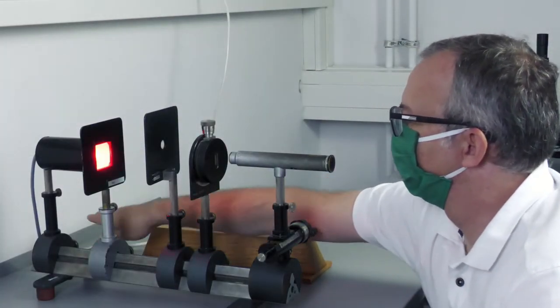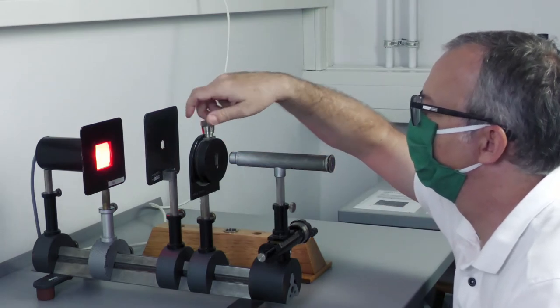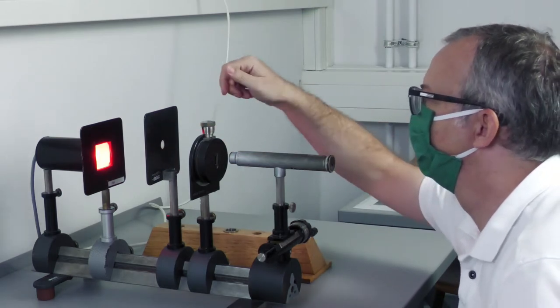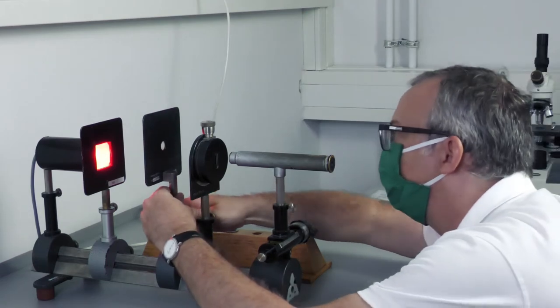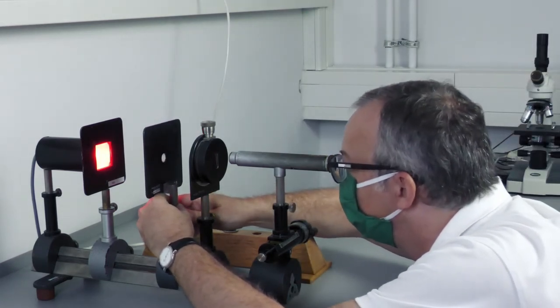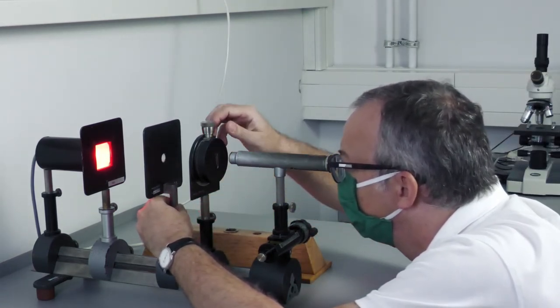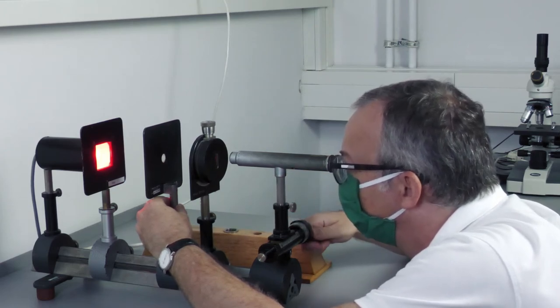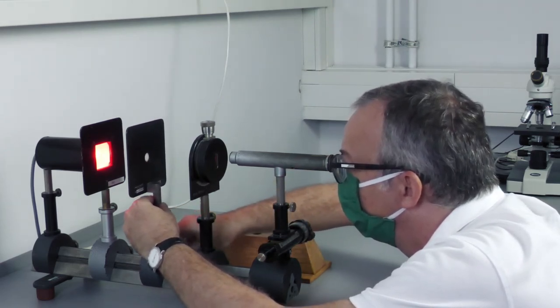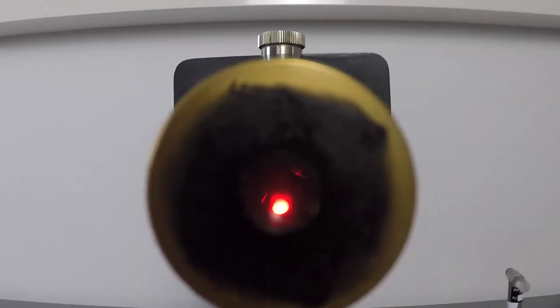First of all, the lamp, color filter, glass scale, tube, and the slit placed directly in front of the lens of the tube is used. With the slit opened as wide as possible, shift the glass scale until its scale appears sharply in the eyepiece of the tube. Then, the slit is closed until the scale division of the scale is no longer resolved.